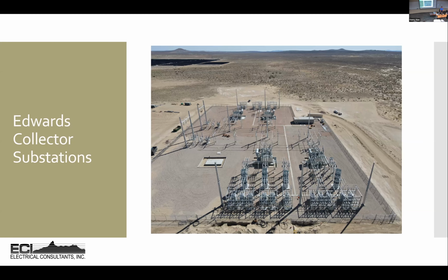So this is one of the substations used to interconnect the facility. Taking a step back on the solar plant itself: the solar panels generate electricity in DC current. That DC current needs to be converted to AC current before it can be transformed to a higher voltage so it can be transmitted to the collector substation. That voltage is 34.5 kV, which is very common in industry for collection voltage. The collector voltage is brought in, metered, and put through another power transformer to convert it to the system voltage, which for this area is 230,000 volts, or 230 kV.